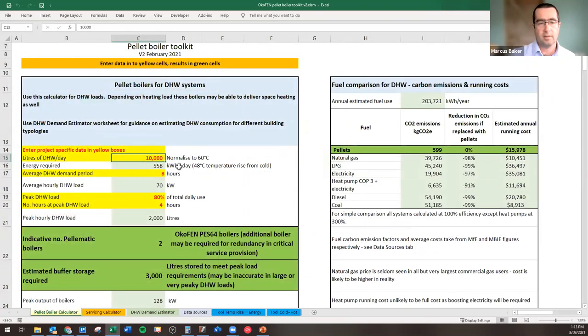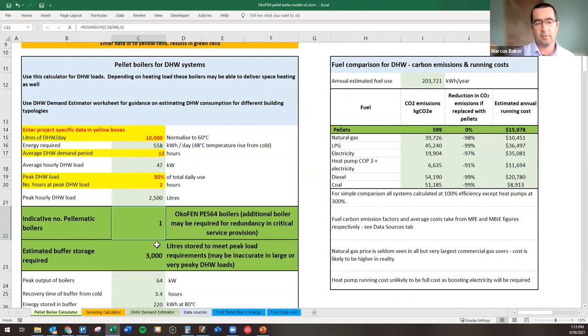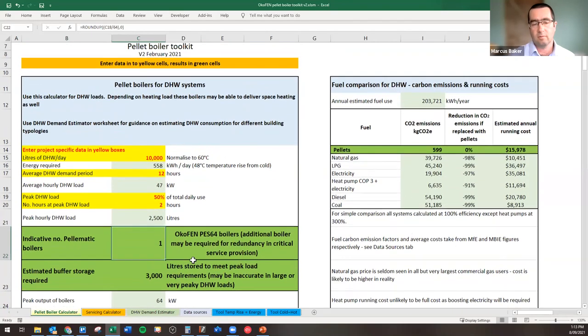So if we just put in 10,000 litres a day, let's say it's over 12 hours and 50% of it is used in 2 hours, then we know our peaky load is about 2,500 liters, and indicative is that one 64 kilowatt boiler will be fine, but as it says here, you might want more for redundancy, and about 3,000 liters. Now these are rough estimates, but it gives you a good idea.